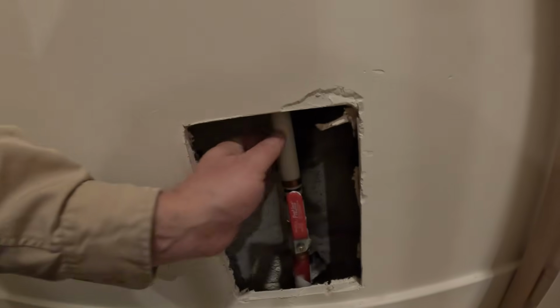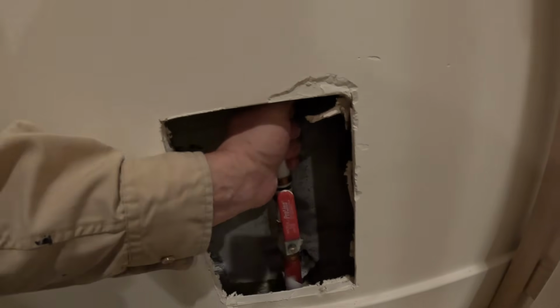But one thing I am looking for is a pressure regulator. That could be another factor in this leak, is having too high water pressure causing problems. I see that all the time. So let's start with one problem at a time. We'll probably go ahead and check the pressure to this home as well in this process. So we'll go ahead and shut this water off now.